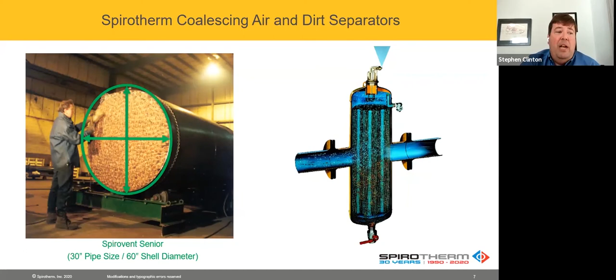Our biggest competitor has always been the traditional separator. In this case, we mocked up a Rolairtrol with our unit, a 4-inch unit, 240 GPM. As we flowed through, we put their unit first, then we put our unit. And if you'll notice, the yellow line is the air removal that's coming out of the Spirotherm. The dark line is coming out of the Rolairtrol.